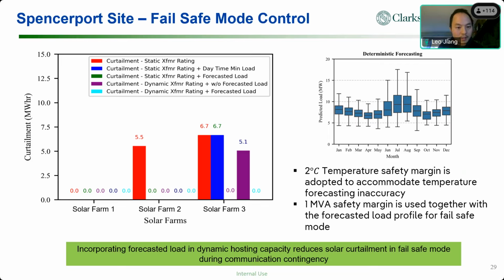And then further, if you look at, let me see, if you use the static transformer rating plus the forecasted load, this site also will almost get rid of the curtailment when you use the dynamic hosting capacity. In our study, we also put a 2°C temperature safety margin in the forecasting, just to accommodate any forecasting inaccuracy. On top of that, we also put in a 1 MVA safety margin.